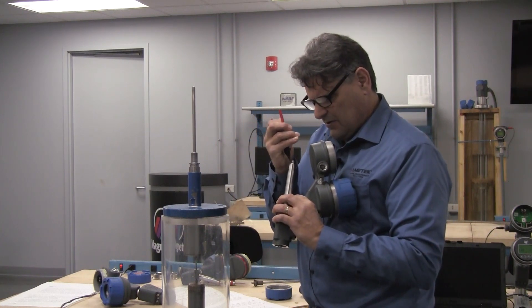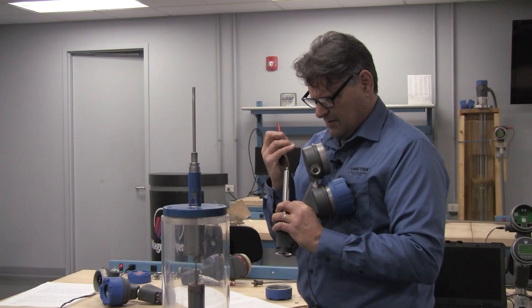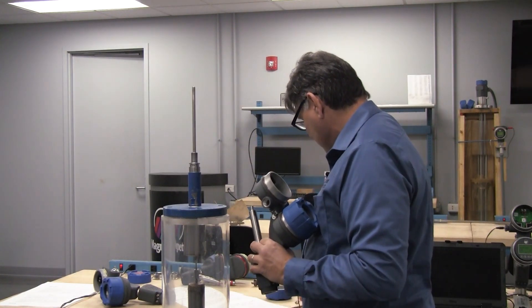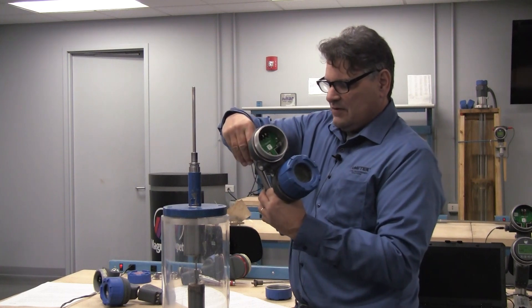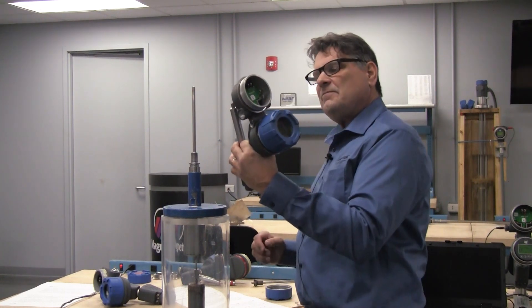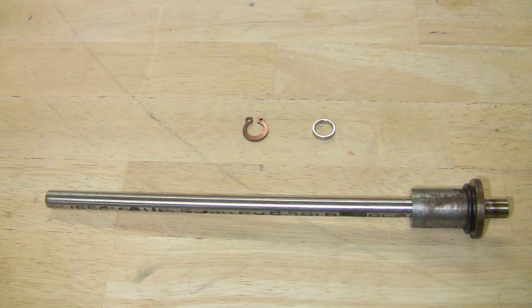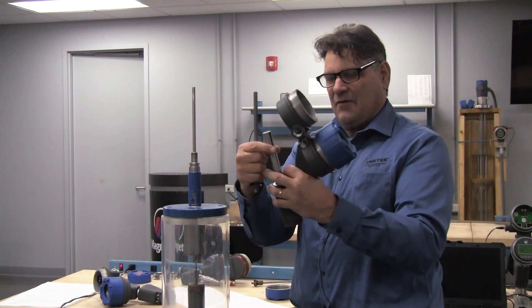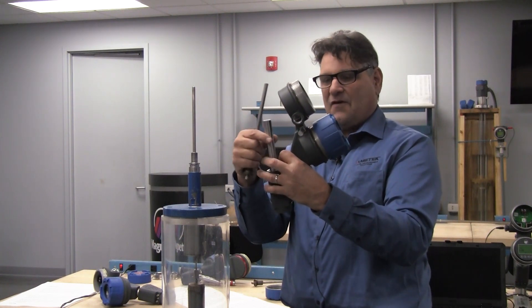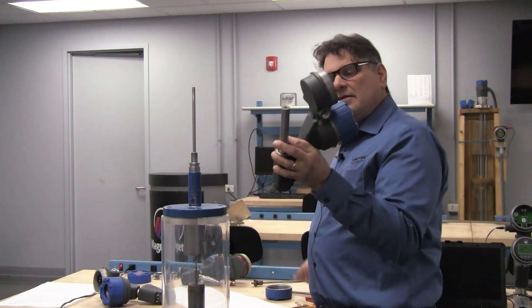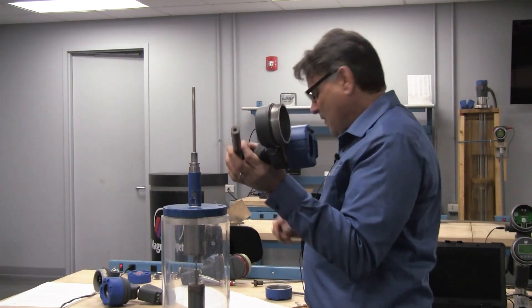So now to put it on, we're going to remove the snap ring. And what's nice now is you'll have two snap rings and two washers, they're small pieces, so just in case you lose them, you'll have those. You're now ready to remove your dummy enclosing tube. So now notice, the LVDT is now free, and we're ready to go ahead and put this on the existing process.